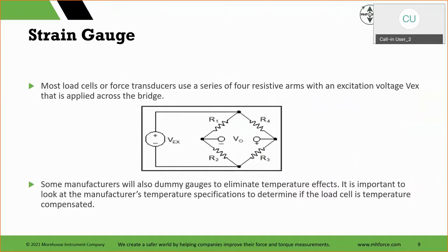If you're not sending that with your equipment for calibration, which you absolutely should, the lab should not be doing a 10-volt DC excitation. They should be doing a 5-volt DC excitation. So it's really important to match the excitation and waveform. The best practice is just send the indicator in, marry things as a system, send it all in together. However, I just want to let people know there is a difference.